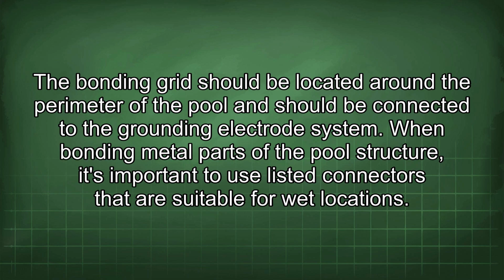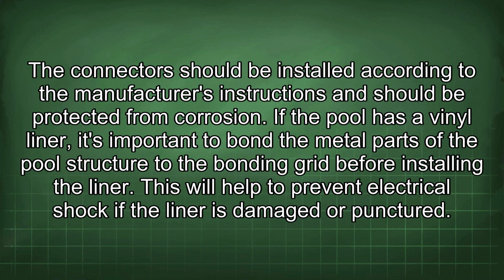When bonding metal parts of the pool structure, it's important to use listed connectors that are suitable for wet locations. The connectors should be installed according to the manufacturer's instructions and should be protected from corrosion. If the pool has a vinyl liner, it's important to bond the metal parts of the pool structure to the bonding grid before installing the liner. This will help to prevent electrical shock if the liner is damaged or punctured.